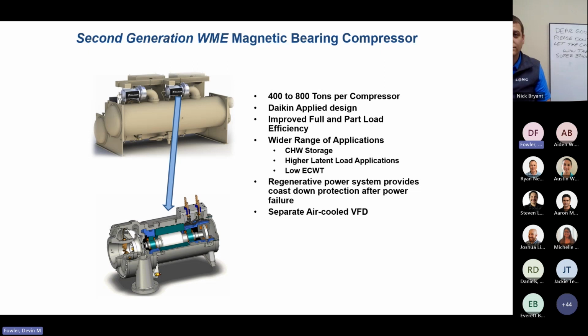We have a regenerative power system. It gives us power to coast down our chillers and keep the bearings operational after a power loss or a power failure. What this does is allow us to turn our motor into a generator, send power back to our capacitor banks on our chillers, and keep those magnetic bearings operating and have the shaft afloat even after a power loss event so that we don't have a hard stop.